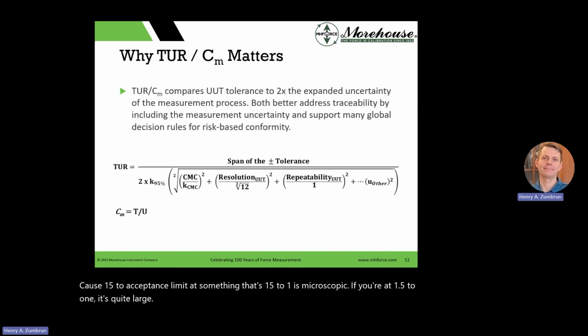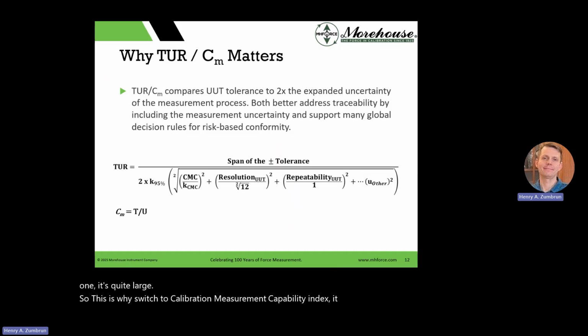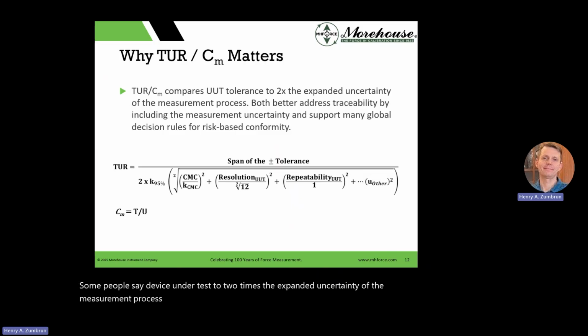So this is why we switch to the calibration measurement capability index. It compares that UUT, unit under test, some people say device under test, to 2 times the expanded uncertainty of the measurement process. Both better address traceability by including measurement uncertainty and support many global decision rules for risk-based conformity. So there you can see it broken down. The span of the tolerance, 2 times K, 95%. The CMC is your calibration and measurement capability.